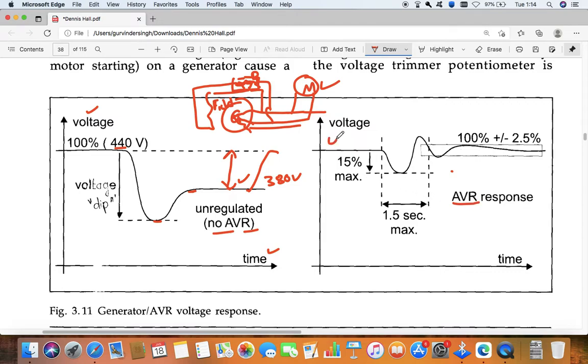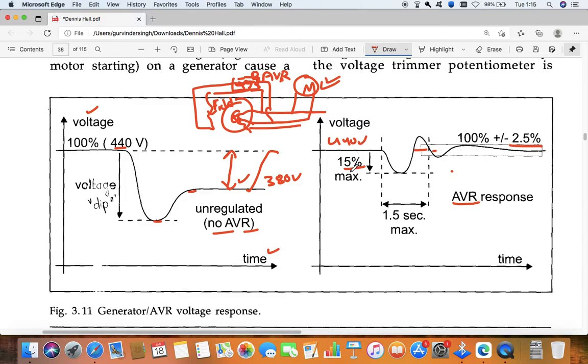So AVR - what actually happens. Now consider this is 440 volt. What will happen when the motor starts and voltage dips more than 15%? It will dip and our AVR will come into action. AVR will give more field excitation current to this field, and this will cause the voltage to come back to its position slowly. It has the capacity to manage the voltage within plus minus 2.5%. AVR will regulate up to that voltage, and it will bring the voltage dip of 15% back to plus minus 2.5% within 1.5 seconds maximum. So it is very quick. If we have AVR in the generator, then we don't have any problem.